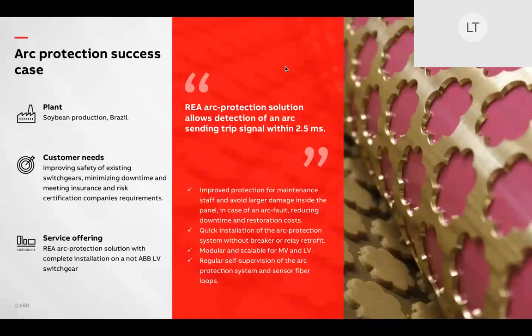The ABB service team locally in Brazil met this challenge and upgraded the protection and control system to the ABB Relion REA Arc Protection Solution. This upgrade was completed in non-ABB low voltage equipment. The addition of our arc detection relays is not specific or unique to just ABB equipment. It can be applied to any third-party low or medium voltage switchgear in your plant. The REA solution provides protection, detection of an arc and sends a trip signal to the breaker within 2.5 milliseconds, reducing the risk of damage to the equipment and saving lives.